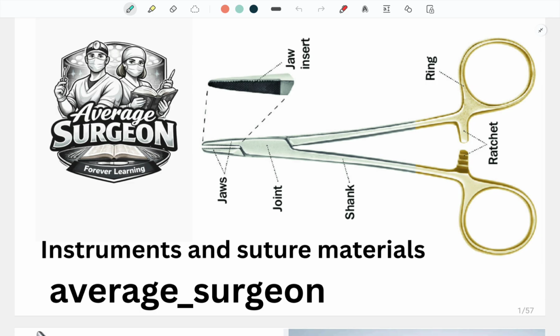Coming to methods of sterilization of instruments, all the instruments are sterilized by autoclave, which is kept at 121 degrees Celsius for 30 minutes. If you are going to put any kind of catheter such as a corrugated rubber drain, or any kind of plastic, or any glassy material or other substances, then depending on the substance there are different sterilization methods. But for autoclave you have to use 121 degrees Celsius for 30 minutes.